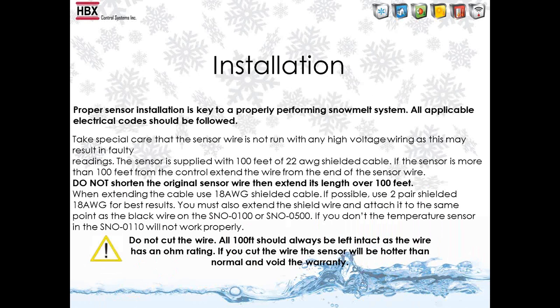Next, we will talk about the installation of the optical snowmelt sensor. The most important thing to keep in mind is not to cut the included 100-foot cable, as this will change the resistance in the control and it will not operate properly. If more than 100 feet is needed, you can extend the cable using two-pair shielded 18-gauge cable up to 200 feet in total length.